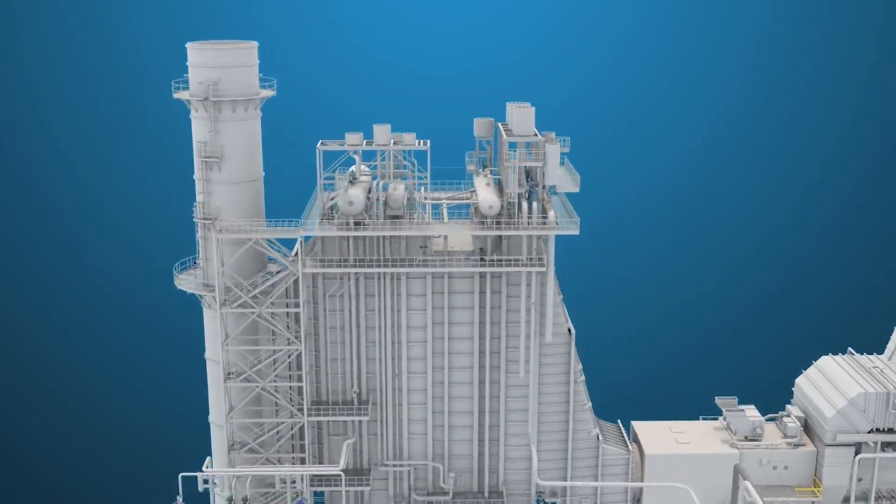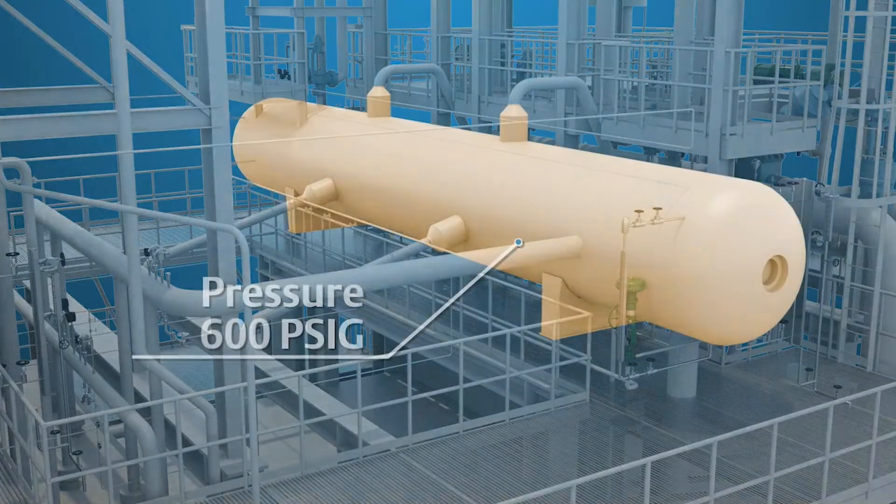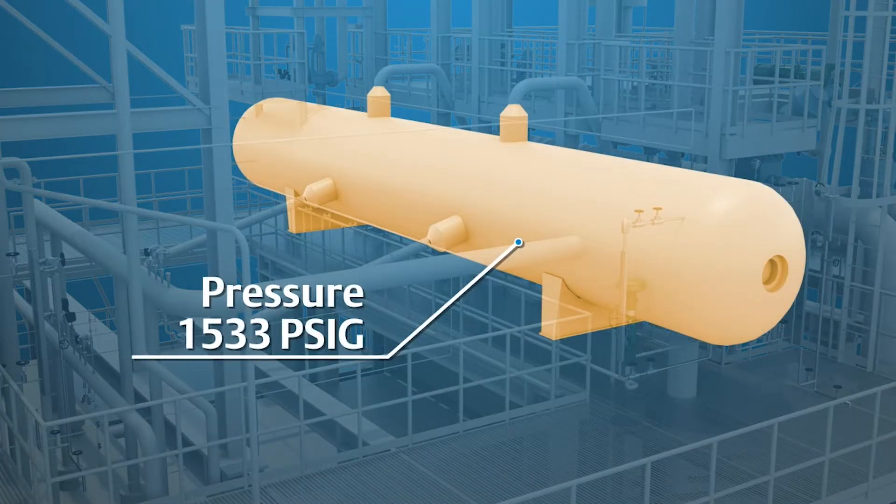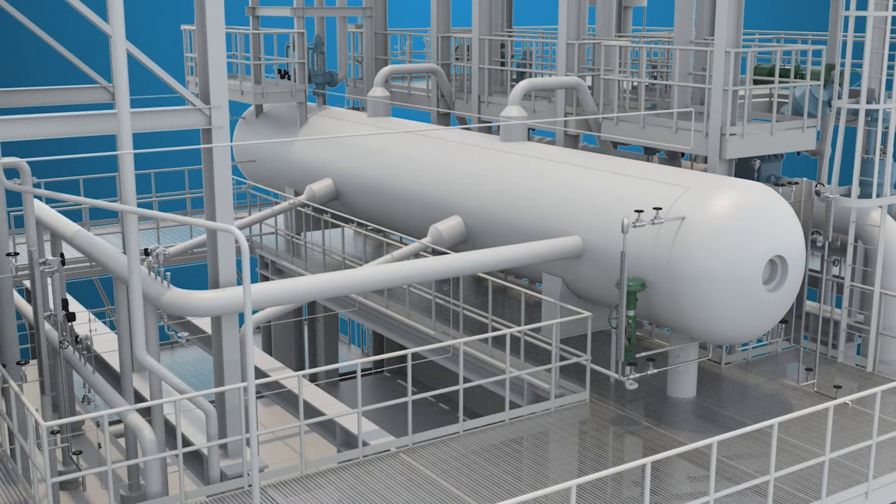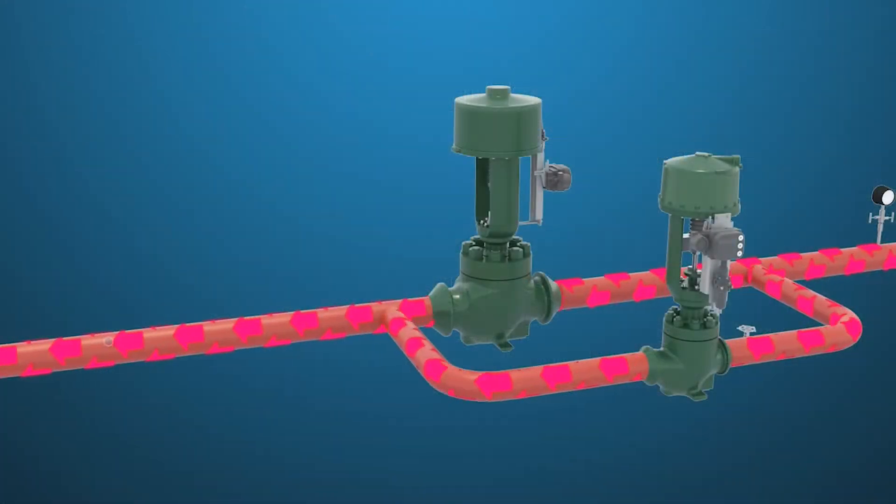As the plant continues to increase load, the HP drum pressure will rise to operating pressure. During this transition, the differential pressure between the drum and feed pump will lower to a point where cavitation is no longer a factor, but increased feed water flow is needed to meet the turbine steam flow demand.